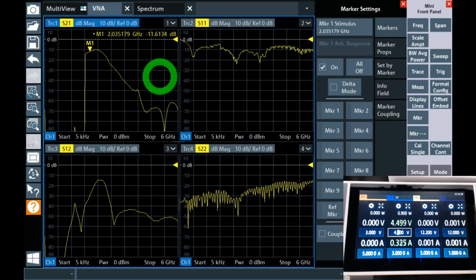It means that it must be deriving the reference point for the power detector to detect when power is present. That reference must be driven somehow by some power supply circuitry, and it's derived from that voltage. And when the power supply reaches some extreme level, that transition point indeed becomes a function of the power supply. So now we can go ahead and record that as one of the behaviors of this DUT. And look how nice it was to just jump back to the network analyzer measurements on the same instrument. We don't have to change anything. Anyway, so we recorded that now.